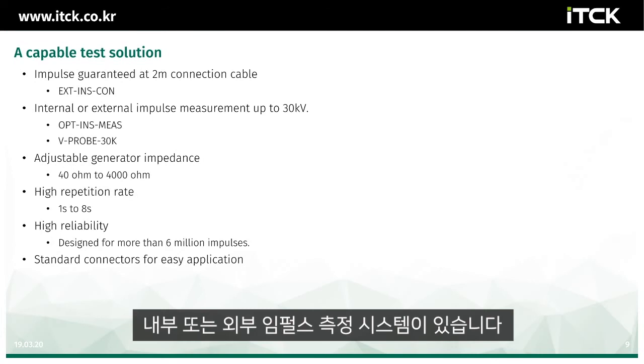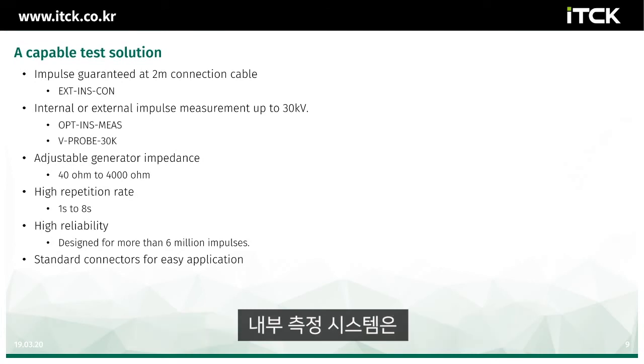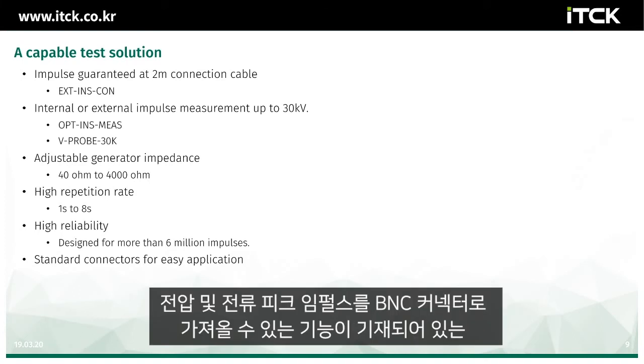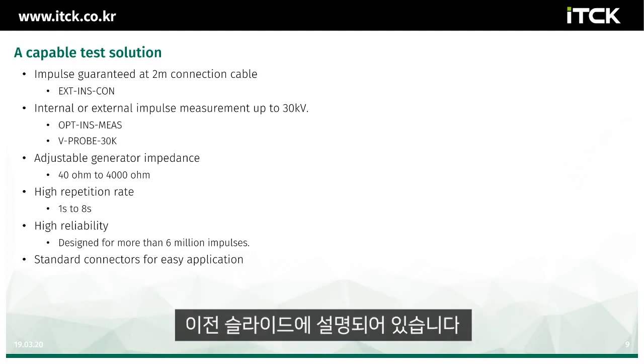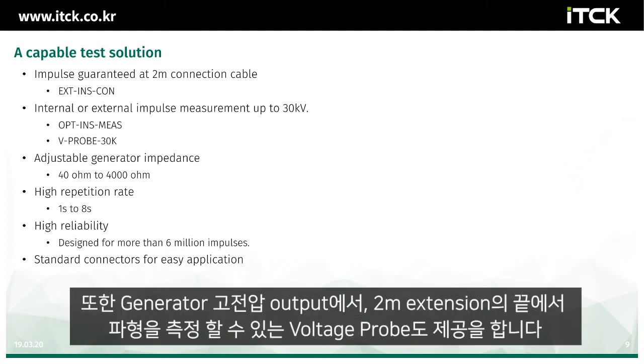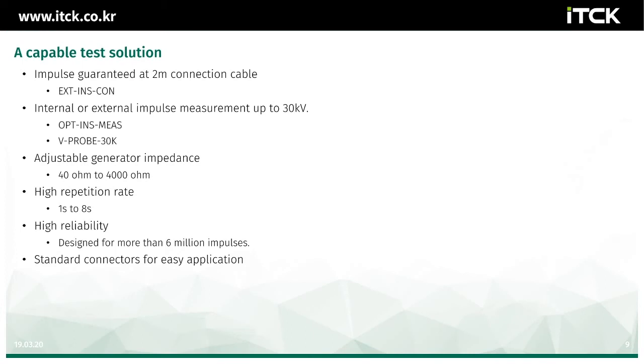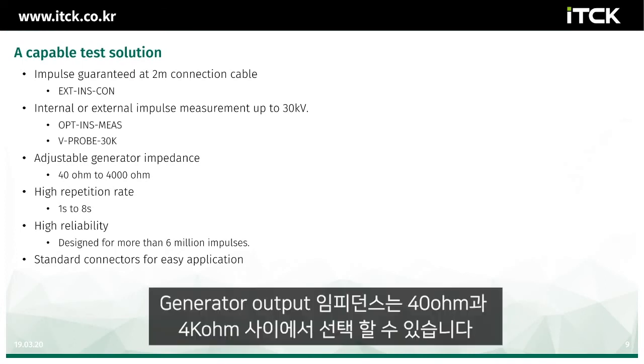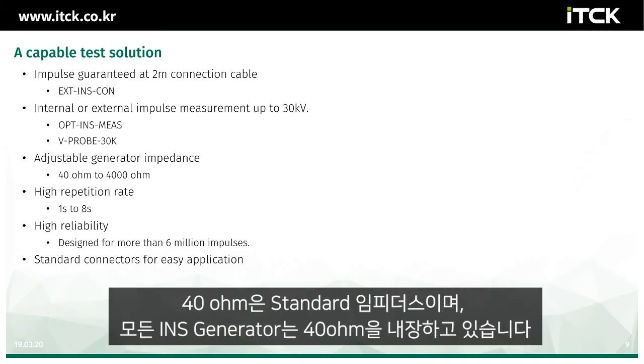We have an internal or external impulse measurement system. The internal measurement system I described in the previous slide, where we can bring the voltage and current peak impulses out to the BNC connectors. In addition, we offer a 30 kilovolt high voltage probe, which can be used directly on the generator high voltage outputs or also at the end of the 2-meter connection cable. The generator output impedance can be adjusted between 40 ohms and 4 kilo ohm. 40 ohms is the standard impedance that we deliver with every INS generator.